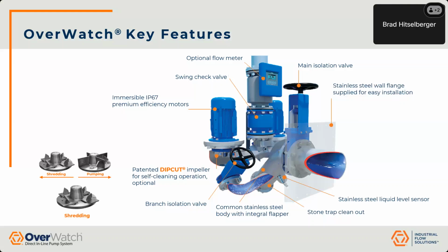There have been instances out in the field where they have withstood longer than that, but that is the guaranteed rating for these immersible motors. So they're not intended to run 24/7 submerged, but if there's a situation where they do need to run submerged, they can. The swing check valve is right here above the discharge. That's something we provide as well. There's an optional flow meter that we would provide, and then there's a main isolation valve as well.